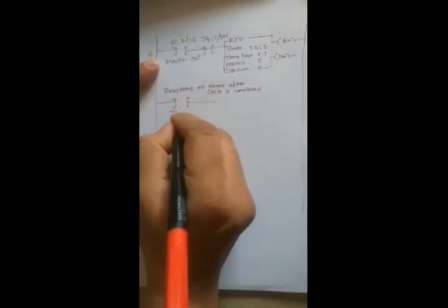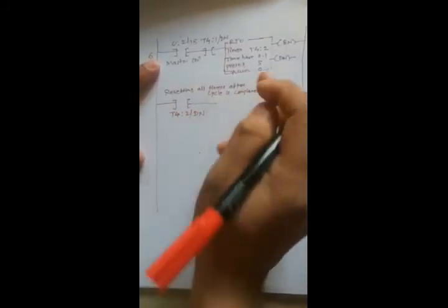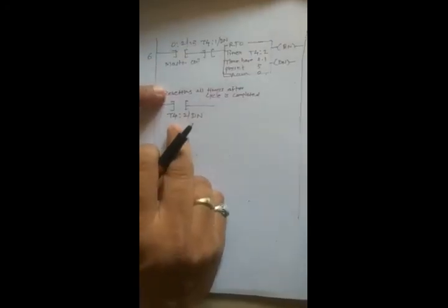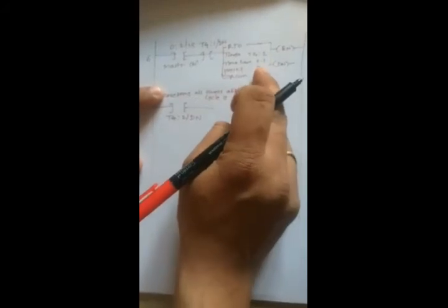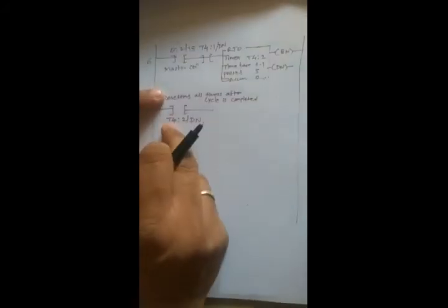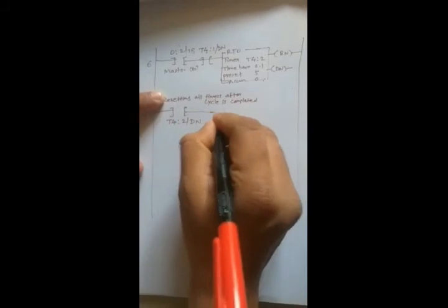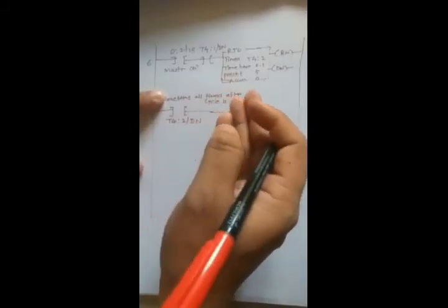Here you can interlink the T4:2 done bit. So the last timer's done bit you have to interlink over here. Once this timing is completed, when the accumulator value becomes equal to the preset value, the done bit will be activated and this contact will become true. So when this becomes true, you have to reset all the timers.